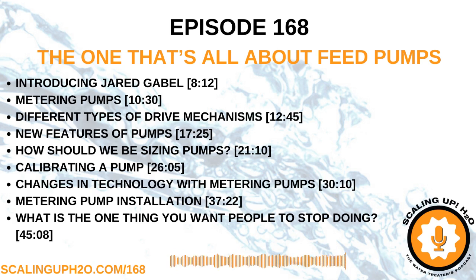But if the flow is positive on the suction side, it's just going to push right up if there's not enough back pressure on the discharge side to keep it from doing that. So be mindful of scenarios where you could siphon or just dump your tank overnight, because that's never a fun scenario, especially if you have an inspector coming out the next day and you've just dumped your entire batch of sodium bisulfite into a tank. You don't want to do that.